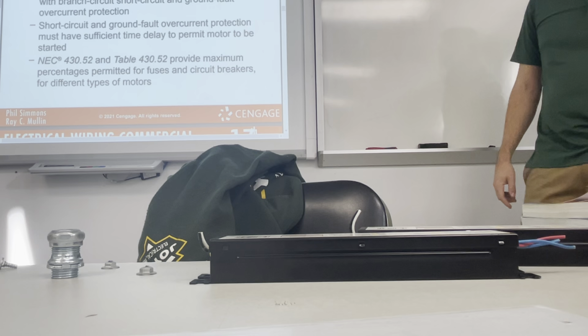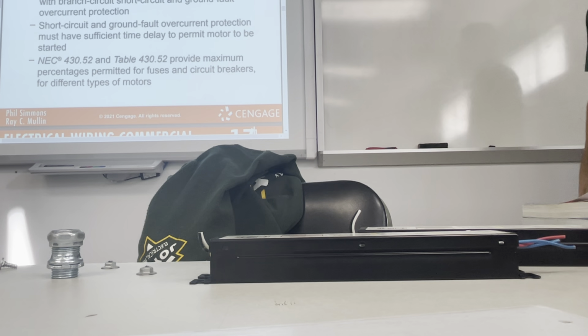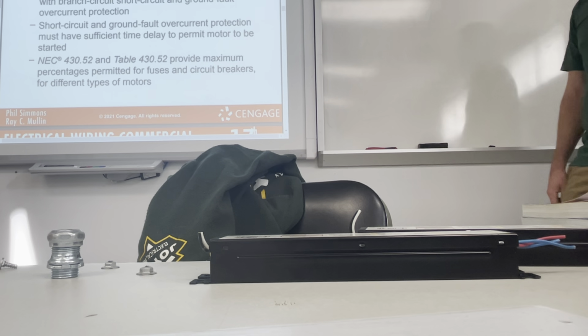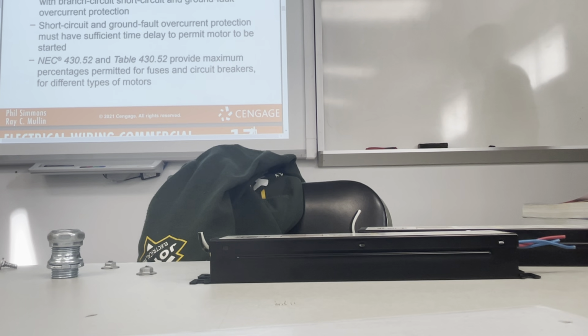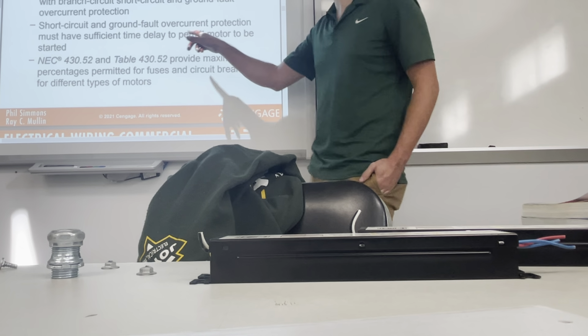Motor branch circuit, short circuit, and ground fault protection. Basics of typical motor installations. Conductors, controllers, and motor must be provided with branch circuit, short circuit, ground fault overcurrent protection. Short circuit and ground fault overcurrent protection must have sufficient time delay to permit the motor to be started. NEC 430 and Table 430 provide maximum percentages permitted for fuses and circuit breakers for different types of motors. Yeah, so it must have sufficient time delay to permit the motor to be started.